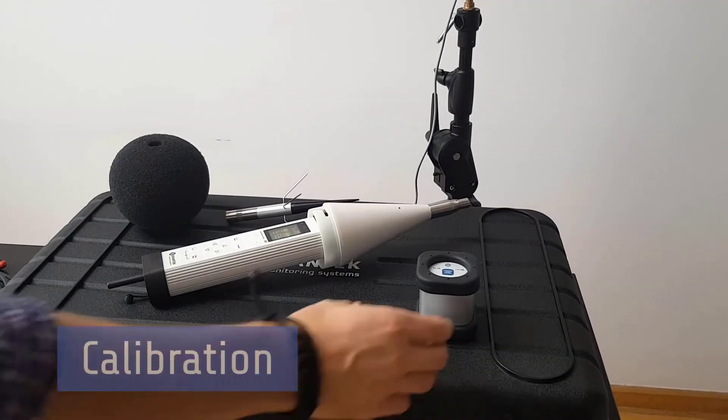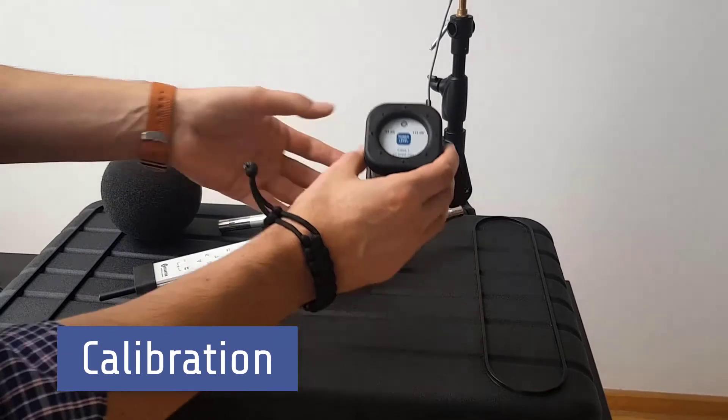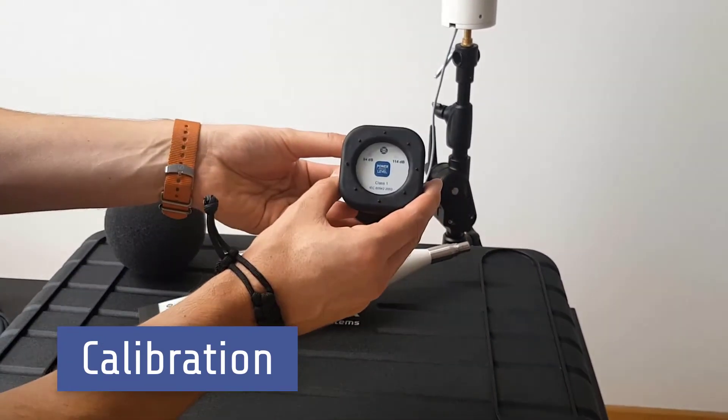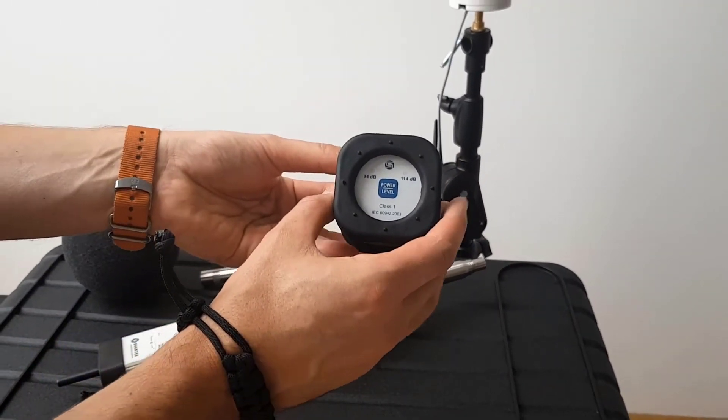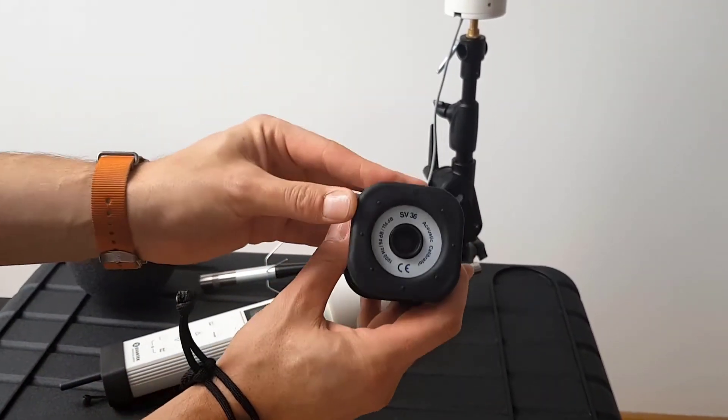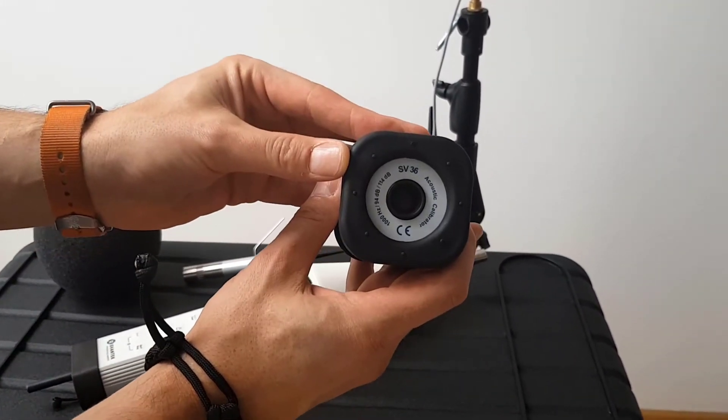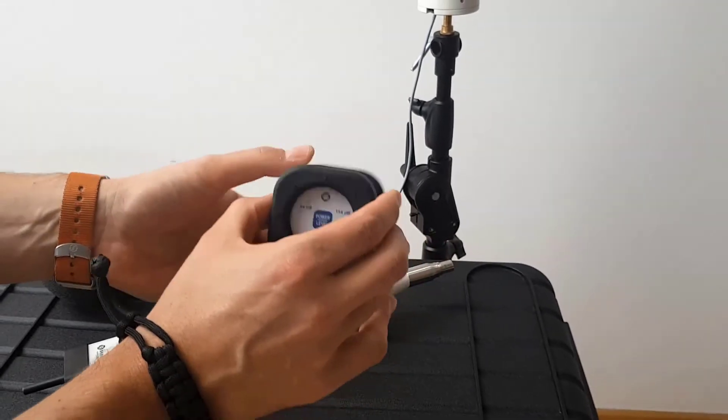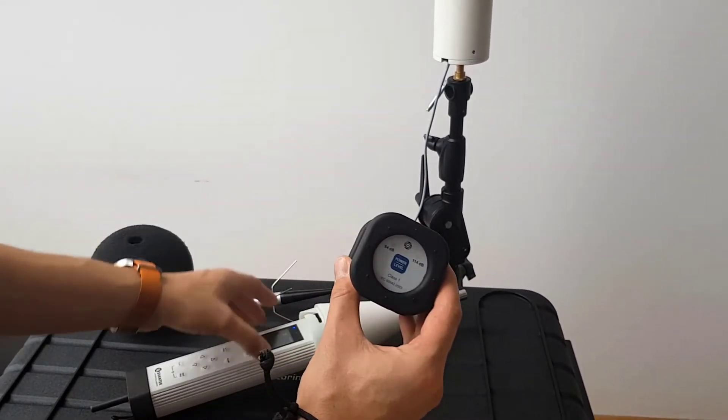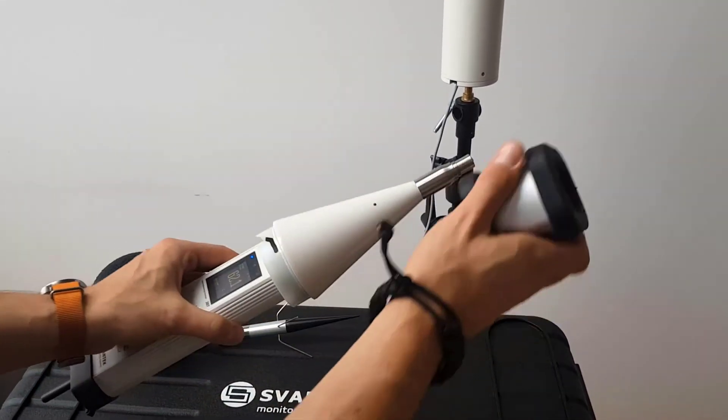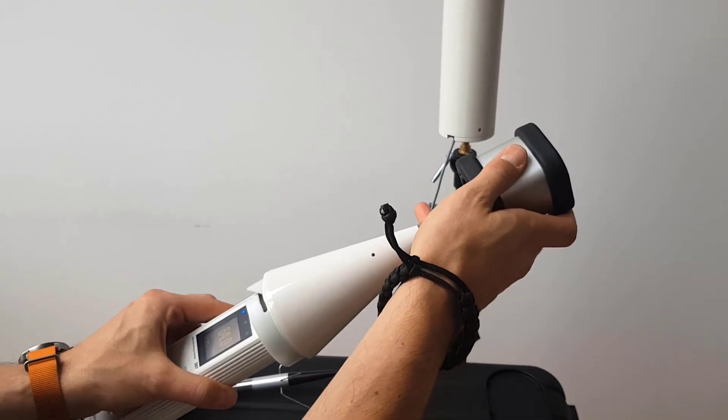The instrument can be easily calibrated in the field using an acoustic calibrator and can perform a patented system check with an in-built reference sound source producing levels of 100 decibels at 1 kilohertz.